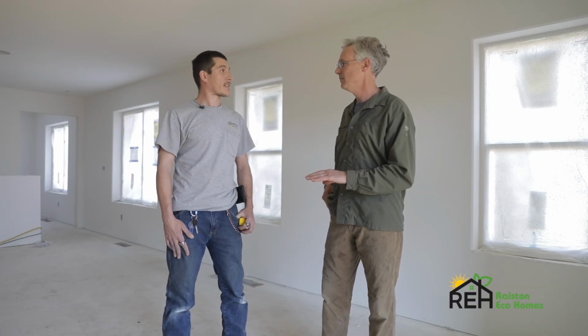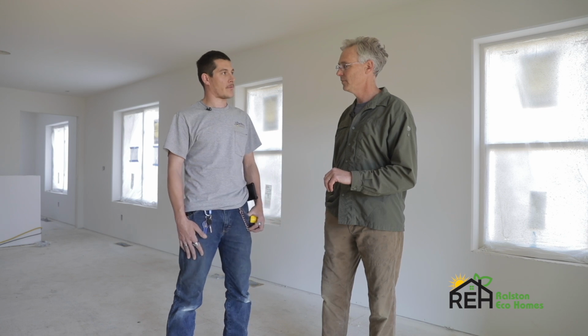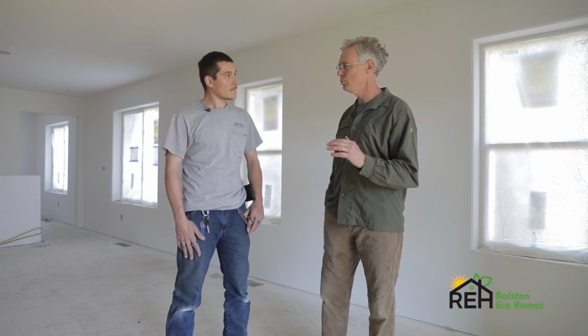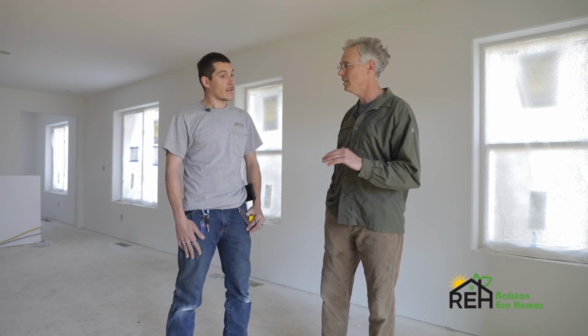Yeah. And then what number did we get down to? Right about 26 CFM, which is about an 83% reduction. So we were around 2% or 3% leakage? 2.2, yeah, which I think then is instead of a 30 square inch hole, we got it down to a 5 square inch hole. Yeah, got quite a bit of reduction out of that, and so way more efficient.